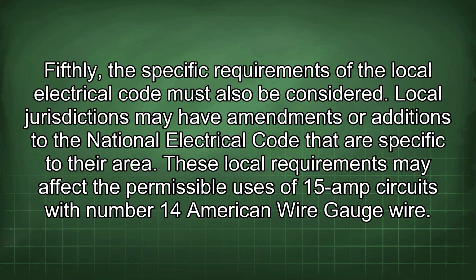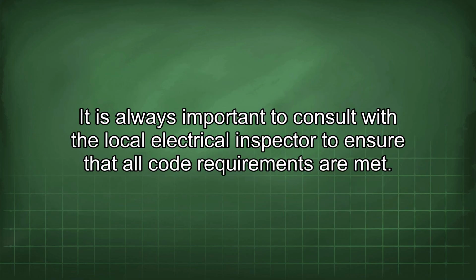Fifthly, the specific requirements of the local electrical code must also be considered. Local jurisdictions may have amendments or additions to the National Electrical Code that are specific to their area. These local requirements may affect the permissible uses of 15 amp circuits with number 14 American wire gauge wire. It is always important to consult with the local electrical inspector to ensure that all code requirements are met.